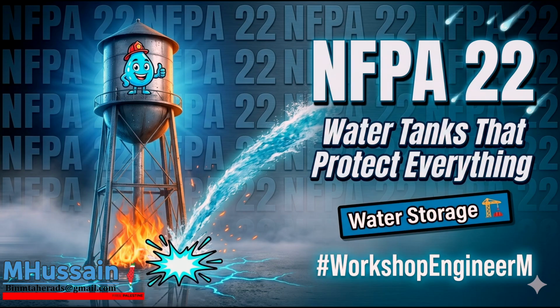Yes, concrete is heavily regulated in the standard. When you commission a newly poured concrete tank, the testing protocol requires you to fill the tank to the brim, and then you are legally required to just walk away and let it sit for a full 24 hours without taking a single measurement. Why is that? Because dry concrete is fundamentally porous. It contains a vast microscopic capillary matrix. When you introduce hundreds of thousands of gallons of water, the concrete physically drinks it. It absorbs the water deep into its structure.